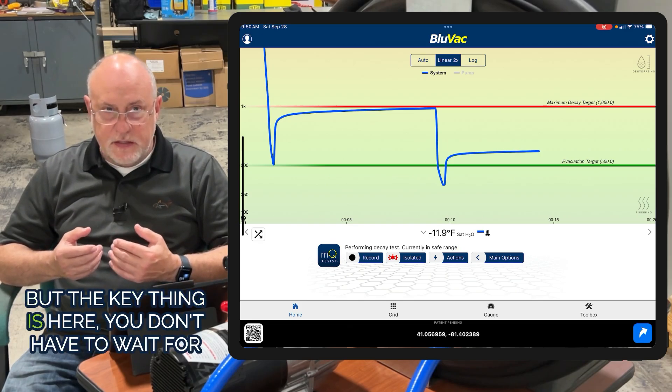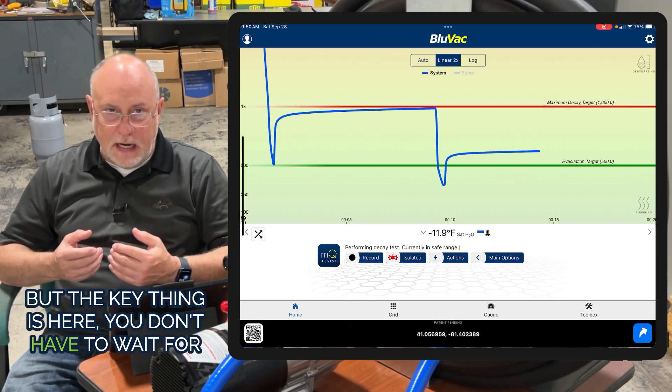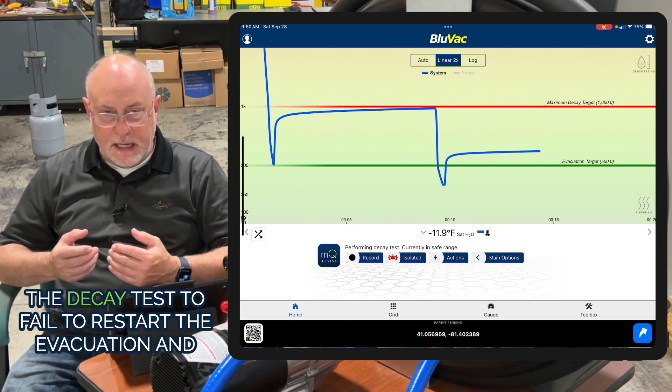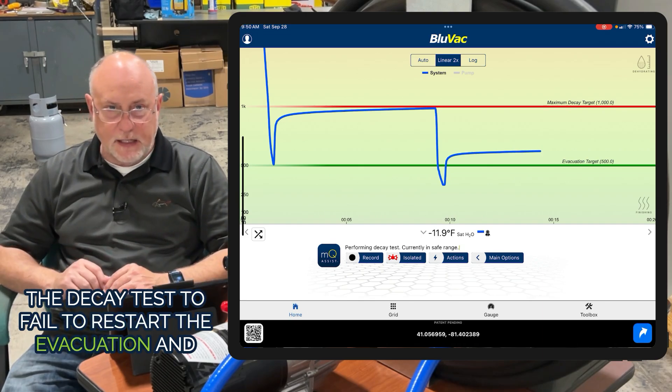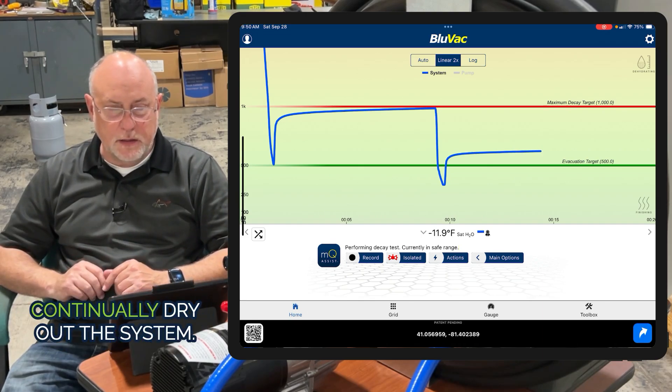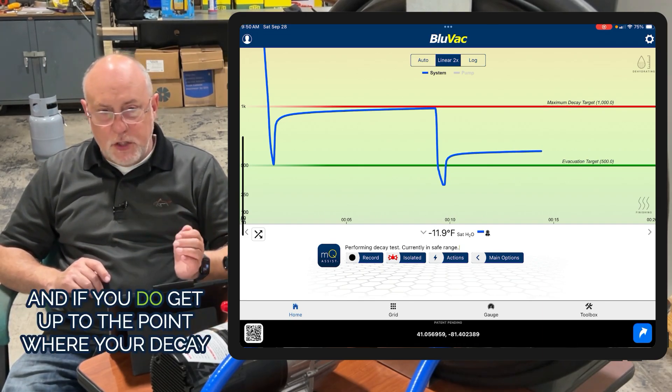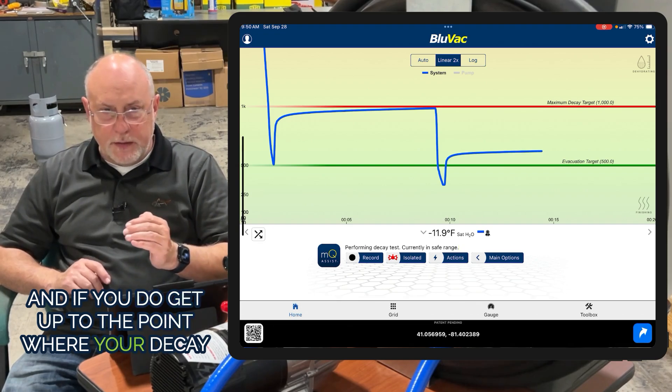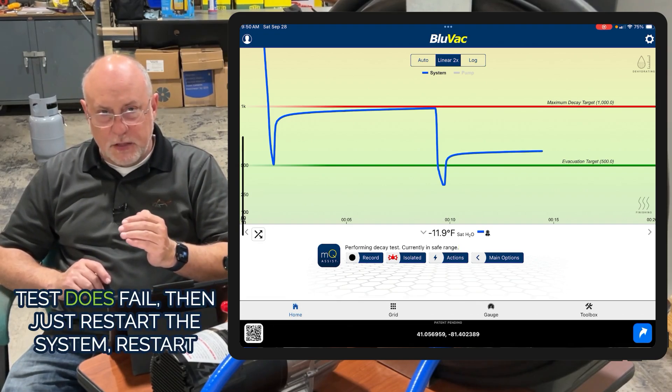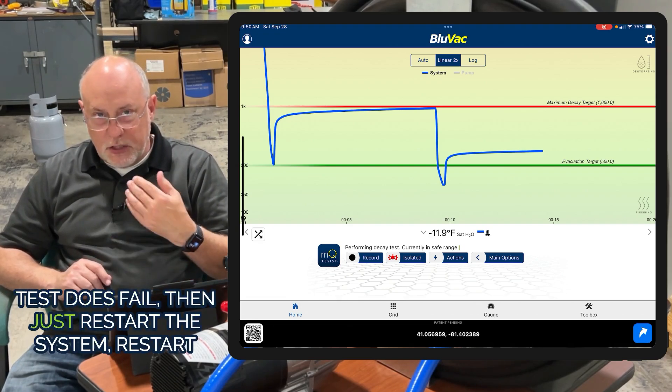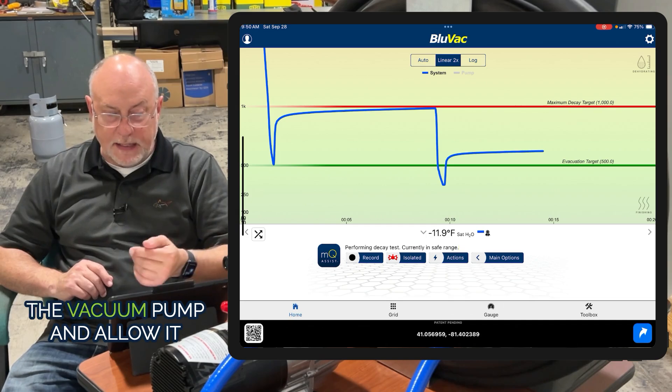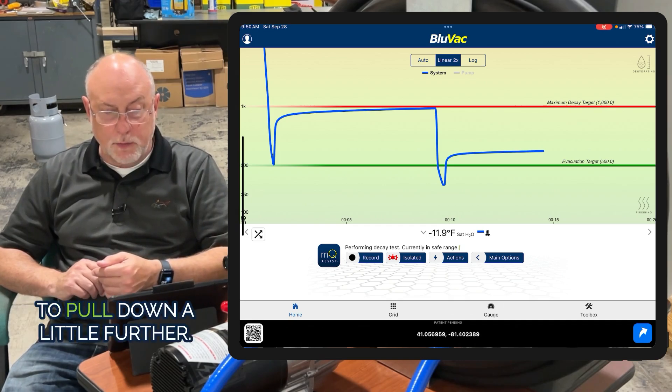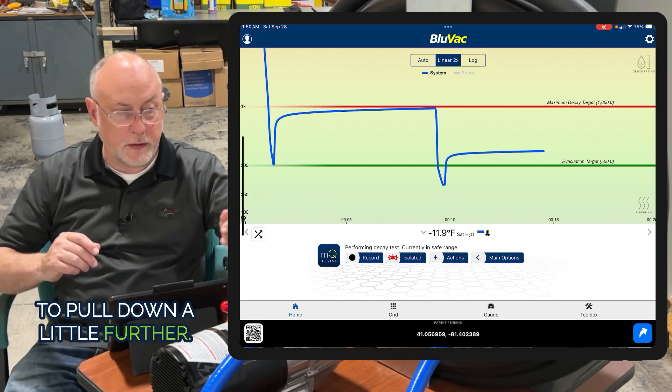The key thing is, you don't have to wait for the decay test to fail to restart the evacuation and continually dry out the system. If you do get to the point where your decay test does fail, just restart the vacuum pump and allow it to pull down a little further.